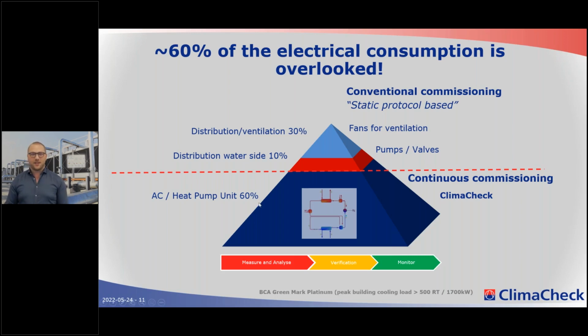What ClimaCheck adds is that we look into the energy production, the source of the energy. That is a huge energy consumer in the system, which means that even if you make great savings - and this is a common thing we see - you do great savings by fixing the pumps, you change the condition, for example the heat pump, so you get a sub-optimization which ends with increased power consumption in total, but you did savings in one part of the system. So to avoid this, we are working very strong to add this analysis.